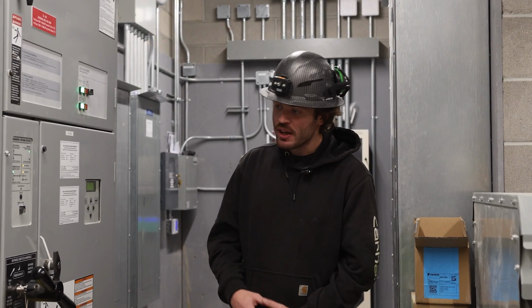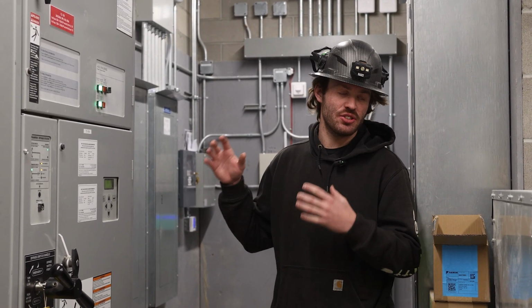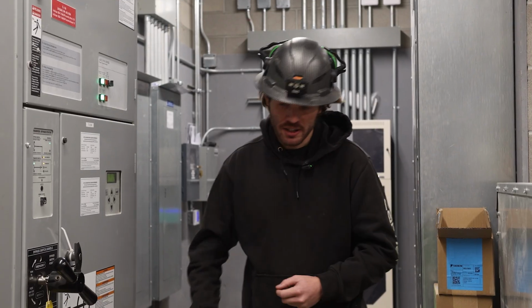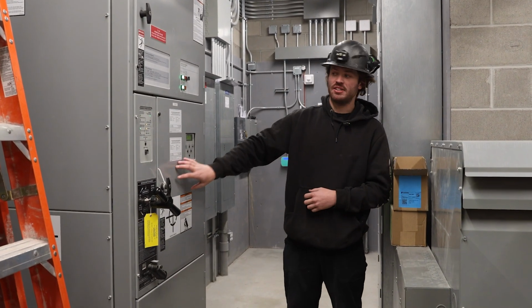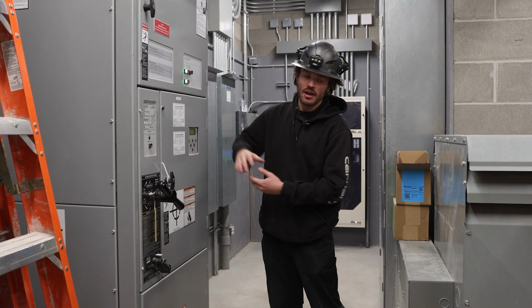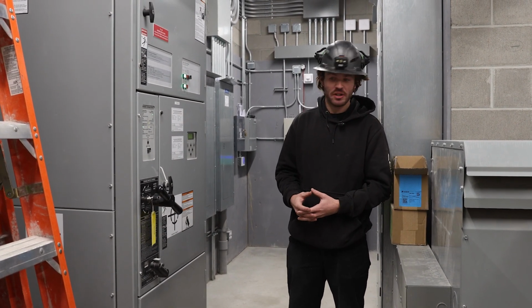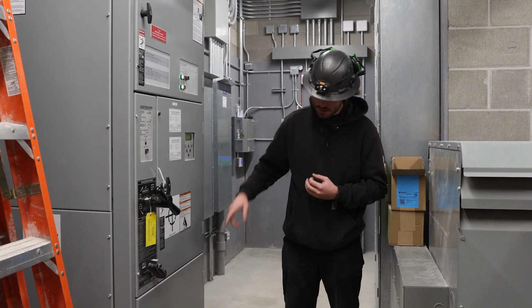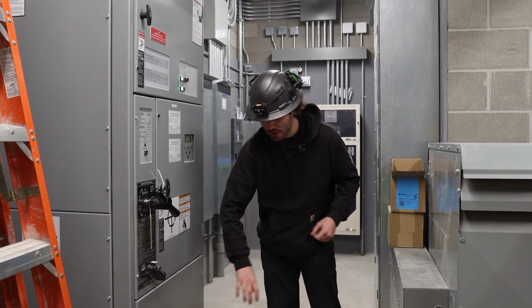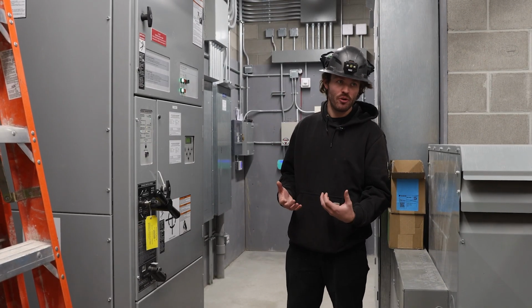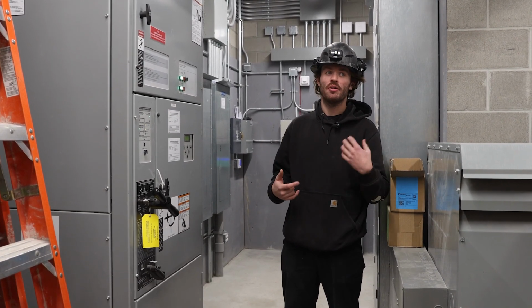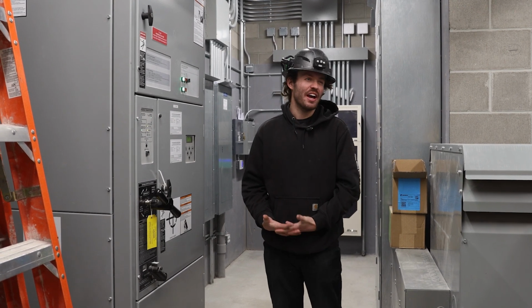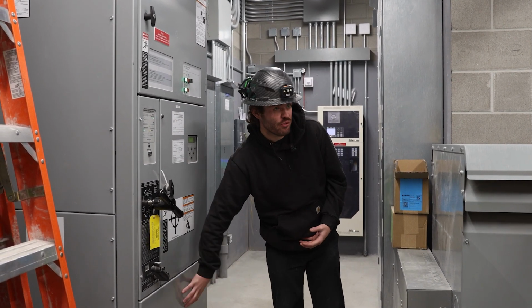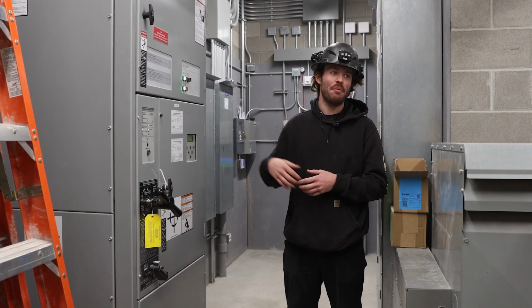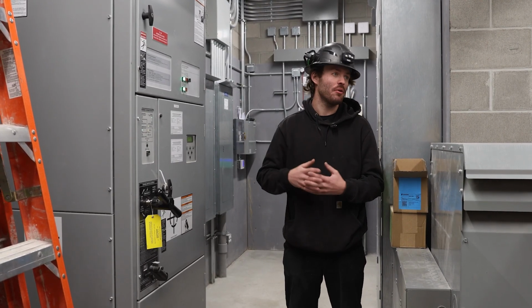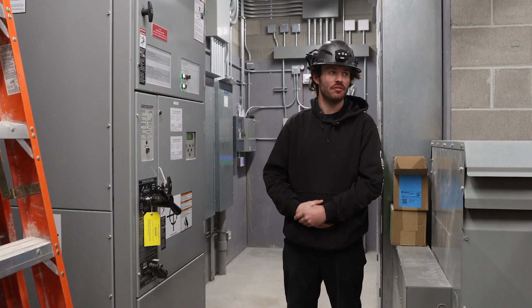The switch itself is a bypass isolation. That means there are two mechanisms inside of this. The automatic mechanism is in the bottom, and the bypass mechanism is about midway up on it. The bypass mechanism is used for servicing of the switch. It'll allow me to bypass power going to the automatic switch so it can be removed, serviced, inspected, and tested without interruption to the building power. Also a handy feature if there was ever an issue or fault with the automatic mechanism, we can then bypass the switch and continue having power without having to do a whole complete recap or something of that nature.